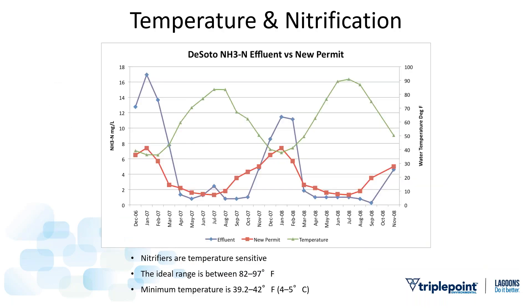Here's some case study data from a lagoon in Iowa. Autotrophic bacteria do exist in wastewater lagoons — you don't need a Nitrox or ammonia removal system to get ammonia out of the water in the summer. In winter, it's not going anywhere, because autotrophic bacteria's activity has slowed so far down that they're barely eating. Looking at the blue line, a lagoon system removes ammonia nicely during the summer months, then you see a real spike in the cold weather months.